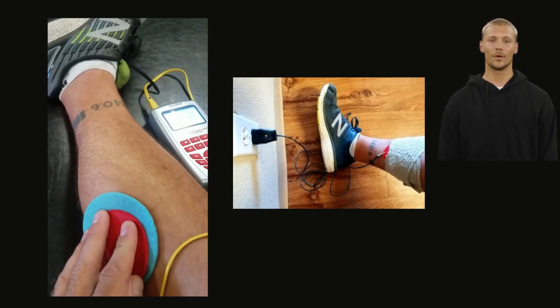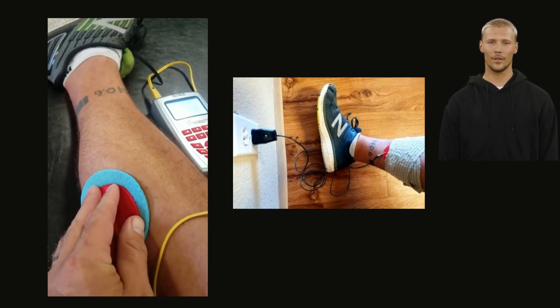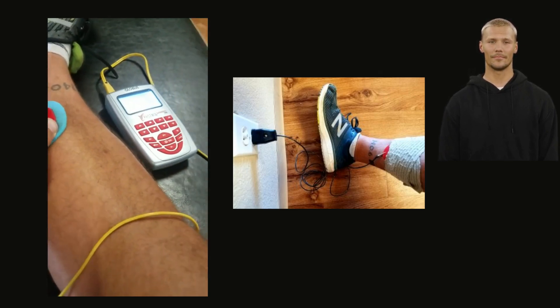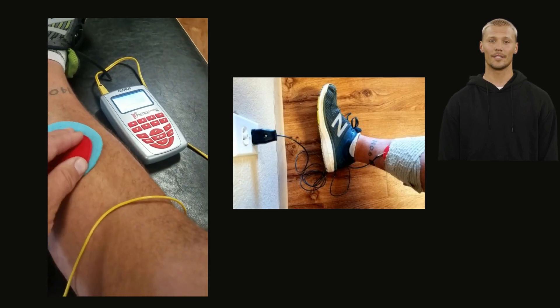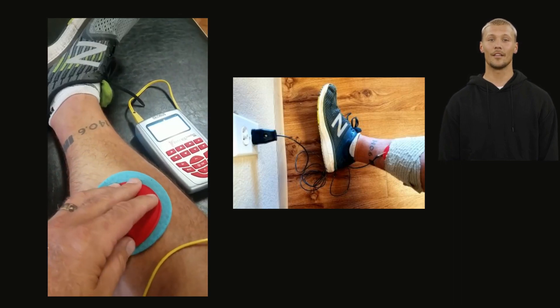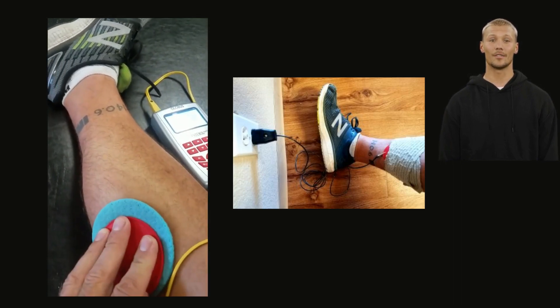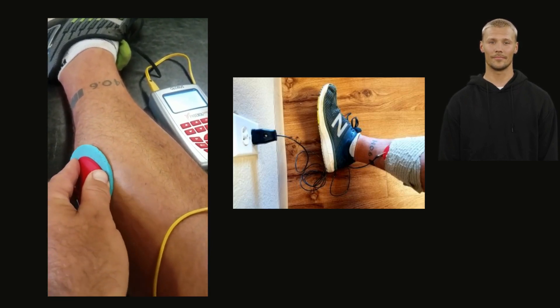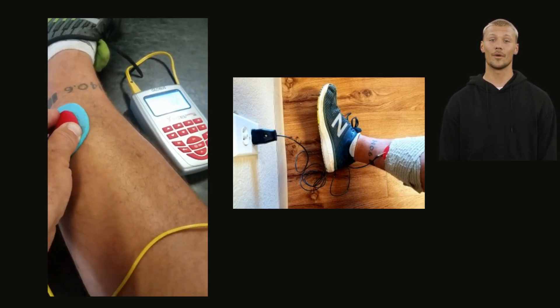Patients suspected of having serious infectious diseases, or diseases that require heat or fevers to be suppressed, should not be treated with electrotherapy. Electrotherapy current should not be applied to the anterior neck, carotid sinus, or through the head. Women who are pregnant should avoid electrotherapy treatment, as safe use has not been established for pregnancy. Patients with cardiac demand pacemakers should not be treated using powered muscle stimulators. If you have any of these contraindications, please contact us or your healthcare provider before using electrical muscle stimulation.